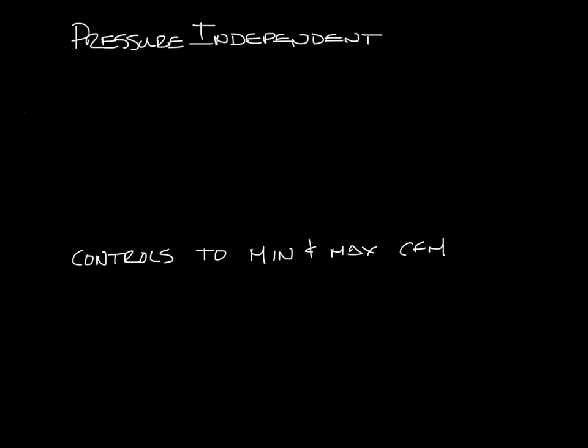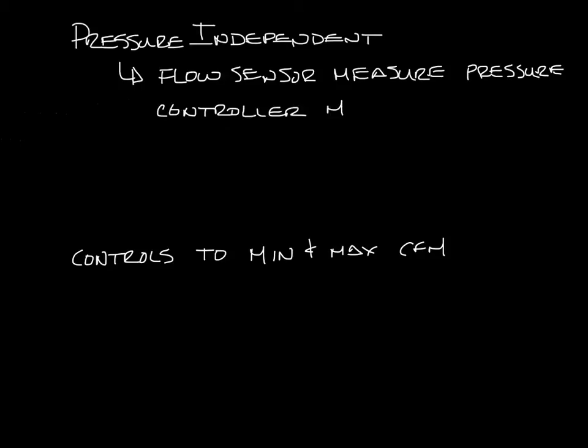I'll put a link to the pressure independent podcast in the notes if you need a full explanation, but here's a quick refresher. A pressure independent VAV box has a flow sensor that measures the pressure in the box and allows the controller to modulate the damper to compensate for changes in the pressure in the system.